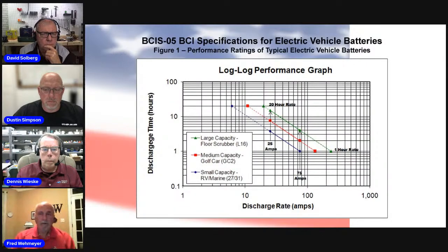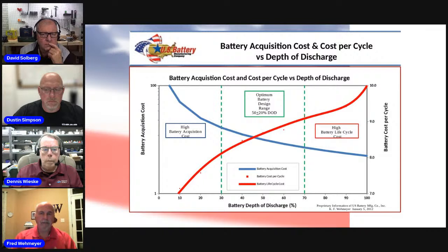And obviously, people ask, well, how many batteries do I need to put in my application? Is one group 24 deep cycle battery enough, or do I need to put in 4 6-volt batteries? And obviously that's a measure of the cost. You're going to pay more for 4 6-volt batteries than you're going to pay for one small 12-volt. But you'll get much longer cycle life because you're going to be managing the depth of discharge. We suggest targeting, if you know what your loads are and about how long you're going to be running them on a daily basis, shoot for about 50%. That gives you the best optimization of initial cost versus life cycle cost.